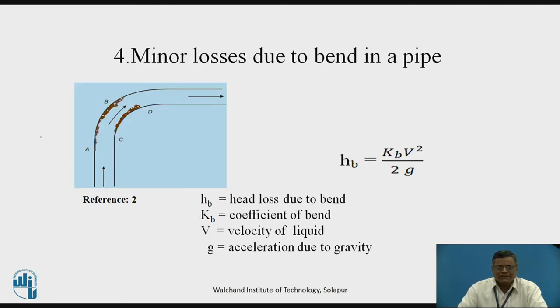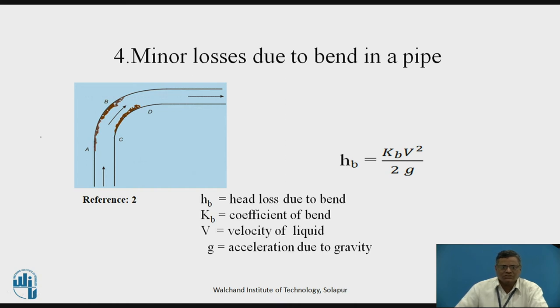Minor losses due to the bend in a pipe. In case of the bend, we have the fluid flowing vertically upwards initially and then changing direction towards the right-hand side. When the liquid changes direction, a head loss occurs. It is purely due to direction change — there is no change in cross-sectional area. The minor loss due to a bend in a pipe is given by: HB = KB × V²/2g, where KB is the coefficient of the bend.